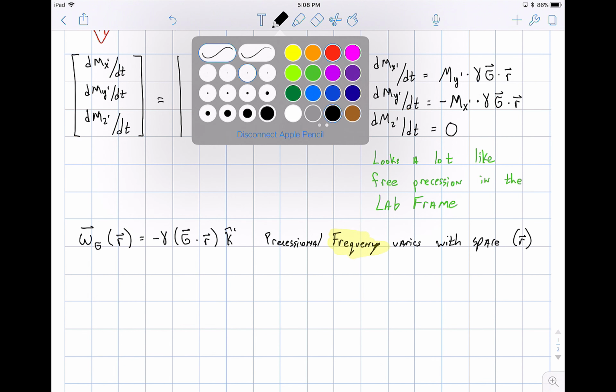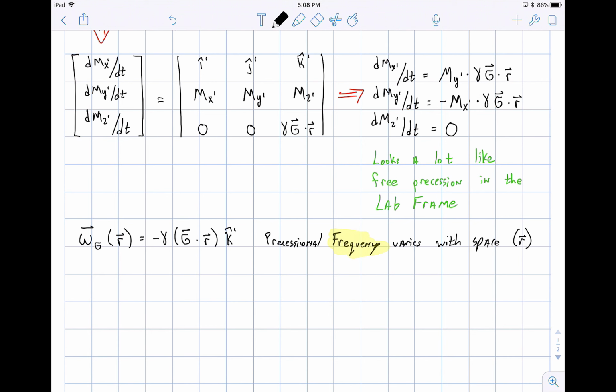There's another thing that can happen, which is what happens to the phase. You have to picture that with the bulk magnetization, I can tip it over with a 90 pulse. Now, gradients can cause that bulk magnetization to precess more quickly, or in fact kind of go the other way if we're thinking about it in the rotating frame. So we can control the frequency. If we can control the frequency of the spins, we can also control the phase of the spins. By tipping the magnetization down with a 90, I can turn a gradient on and give phase to the spins. I'll show this mathematically right now, but if we can manipulate the frequency, we can also manipulate the phase. Both of those are essential concepts.